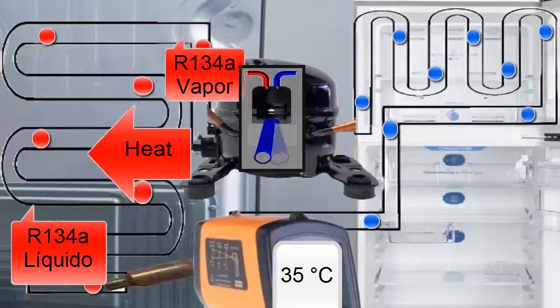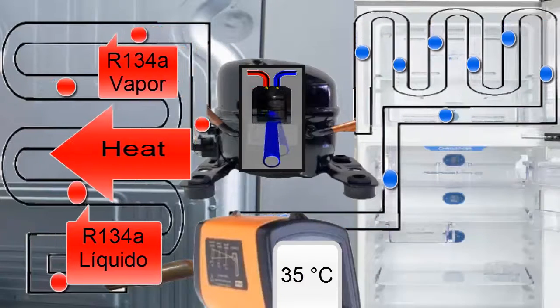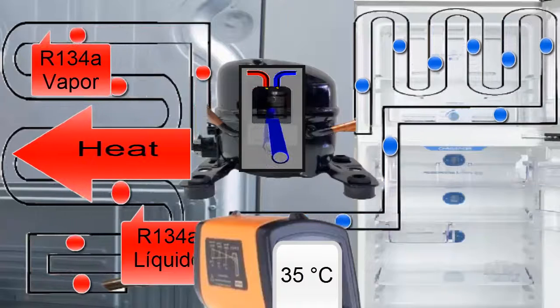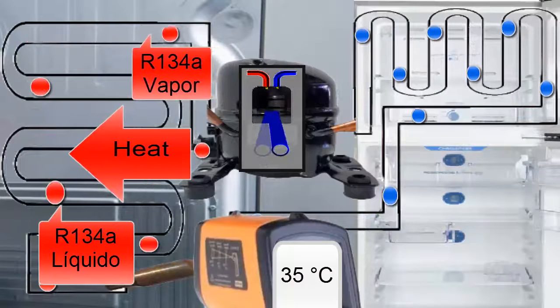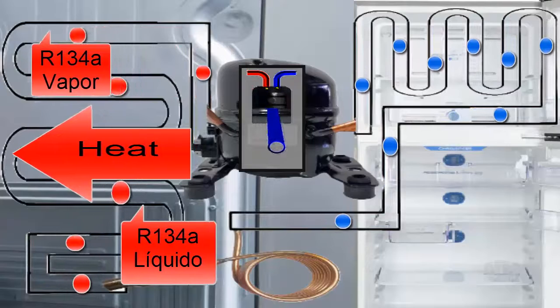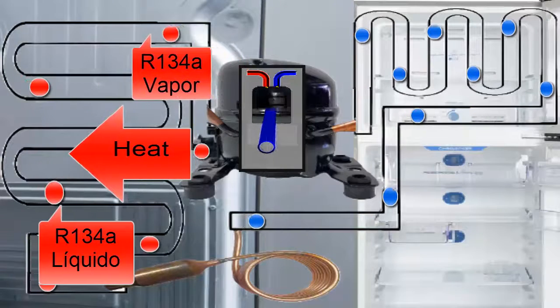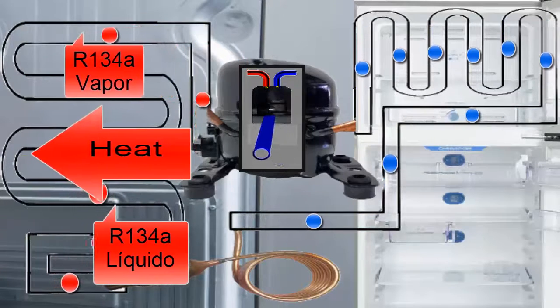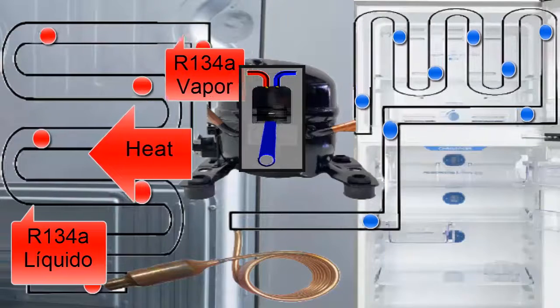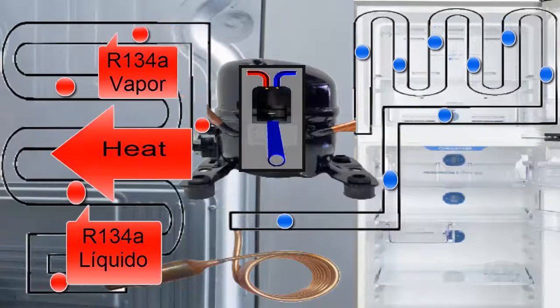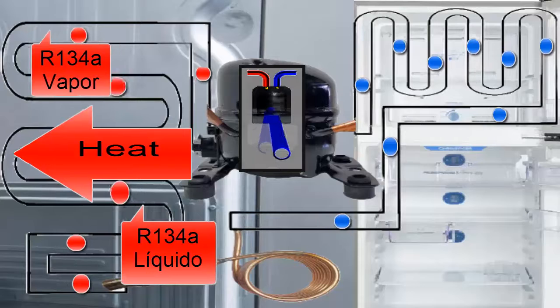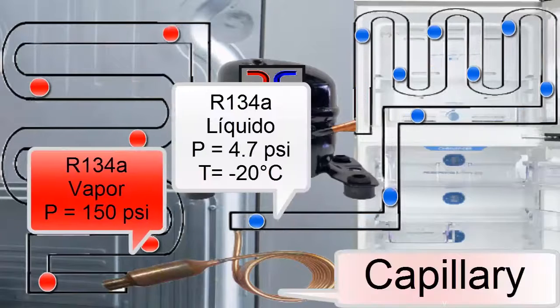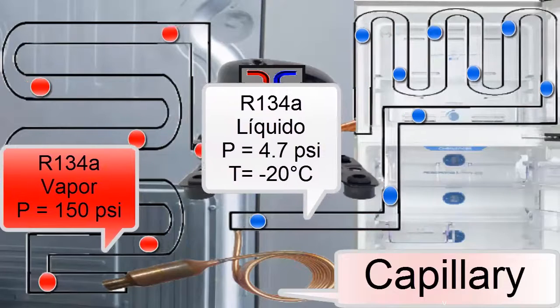The R134A, now in a liquid state and at a temperature close to the ambient, exits the condenser and heads to the capillary tube to restart the cycle. In the capillary, the pressure and temperature of the refrigerant decrease significantly, so it returns to the initial pressure of 4.7 pounds per square inch and minus 20 degrees Celsius, restarting the refrigeration cycle.